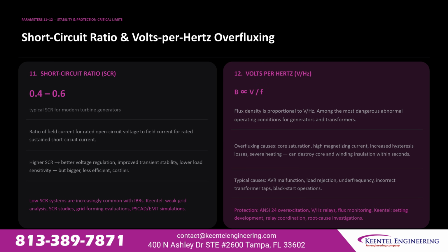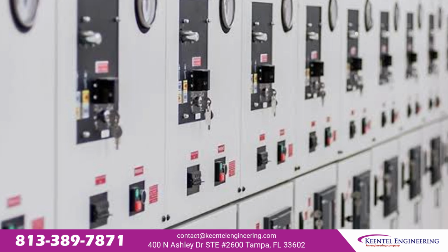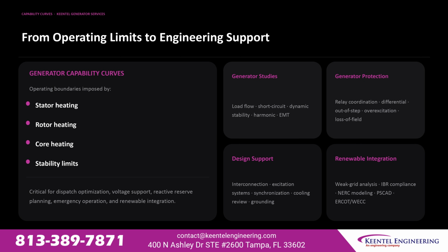Volts-per-Hertz, or overfluxing, is among the most dangerous abnormal operating conditions for generators and transformers. Flux density is proportional to voltage over frequency. Overfluxing causes core saturation and severe heating that can destroy core and winding insulation within seconds. Typical causes include AVR malfunction, load rejection, and underfrequency. Protection relies on ANSI 24 overexcitation relays and flux monitoring. Generator capability curves define operating boundaries imposed by stator heating, rotor heating, core heating, and stability limits, critical for dispatch optimization, voltage support, and renewable integration.